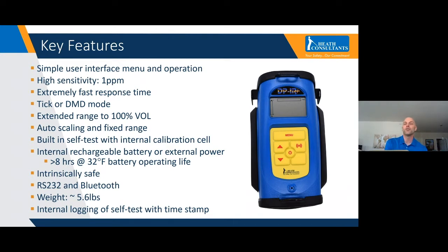That's one of the new improvements we have on the DPIR Plus, is the increased response time. We've actually cut the response time in half for what the unit can detect. There's two modes, I guess, ways to visualize or to hear your leaks. You've got a DMD mode and a tick mode. Not to get too into the weeds, the DMD, it's digital methane detection. If you currently have a DPIR, you most likely use this mode. It's the mode where you hear nothing, it's quiet until you have a gas concentration that reaches your alarm threshold, and you'll get a beep beep beep alarm on that.